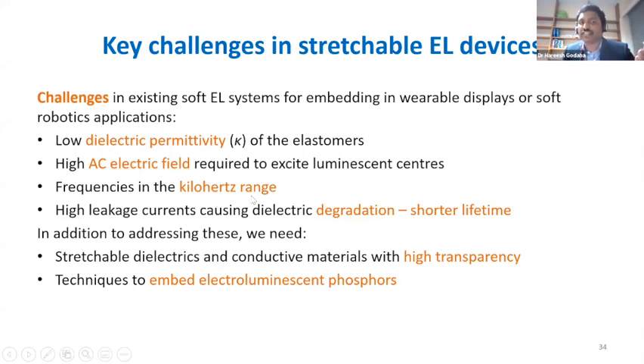So we need a kilohertz range AC signal, which is again also of a high voltage. High leakage currents can also cause dielectric degradation. If there are high leakage currents, this can cause heat in the elastomer, which can cause it to break down.